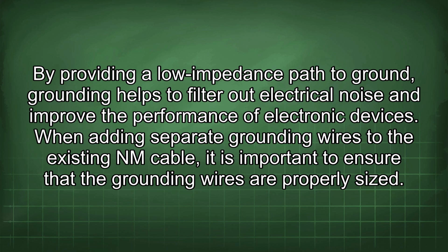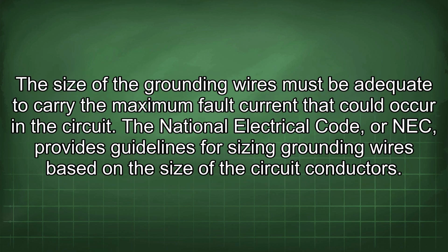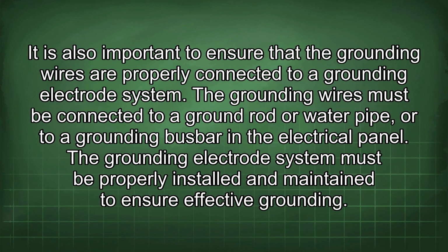When adding separate grounding wires to the existing NM cable, it is important to ensure that the grounding wires are properly sized. The size of the grounding wires must be adequate to carry the maximum fault current that could occur in the circuit. The National Electrical Code, or NEC, provides guidelines for sizing grounding wires based on the size of the circuit conductors. It is also important to ensure that the grounding wires are properly connected to a grounding electrode system. The grounding wires must be connected to a ground rod or water pipe, or to a grounding busbar in the electrical panel. The grounding electrode system must be properly installed and maintained to ensure effective grounding.